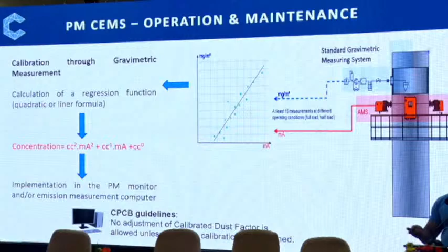This is one of the things about maintenance. A universal fact is that with any kind of equipment, when the manufacturer gives you the operation and maintenance details in the manual, we must follow them because it has been tested. It says how much time your usual maintenance will take, how regularly you should do it, and what precautions you must take. So the operation and maintenance manual of the equipment is not a joke. It is based on the performance and use of that equipment, so you must follow it. Ensure the consumables required for that particular equipment are on the site. It should not be that the consumable is finished, you then place the order, and 3 months of data is not there. Then it is your fault.